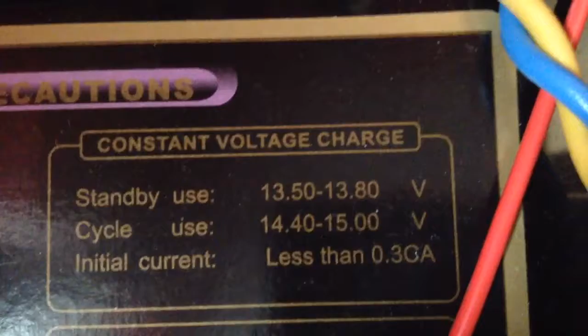If you're using your system daily, that's called cycle use, and the batteries need a higher voltage charge, in this case 14.4 to 15 volts. Remember, these are AGM batteries, and AGM batteries need higher voltage than some other types, like gel batteries.